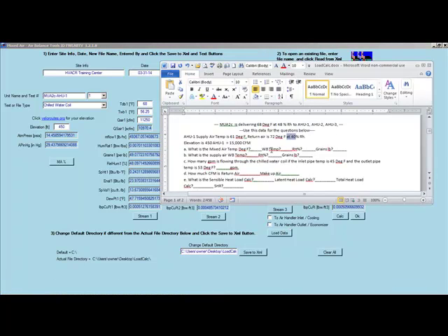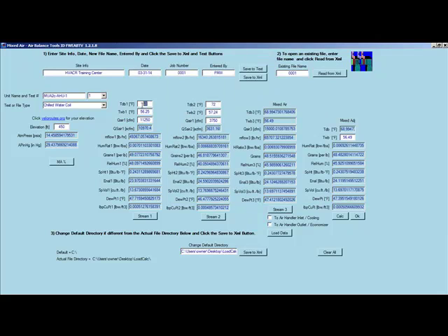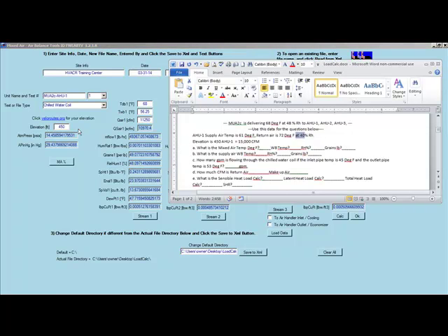So let's take a look at our conditions. The two mixed airs are stream 1 coming from MUA2C would be 68 at 48% RH. So here's 68 and here's 48% RH. Now our elevation is 450 still. Our CFM is 15,000 CFM.